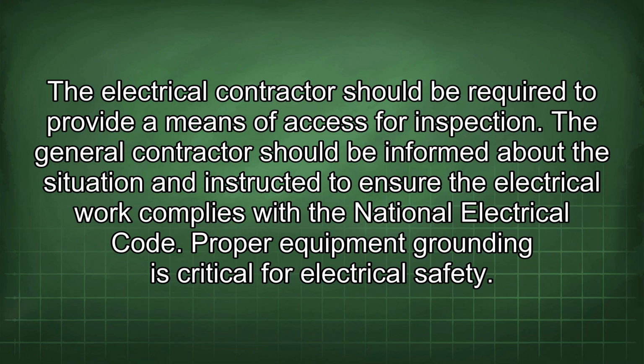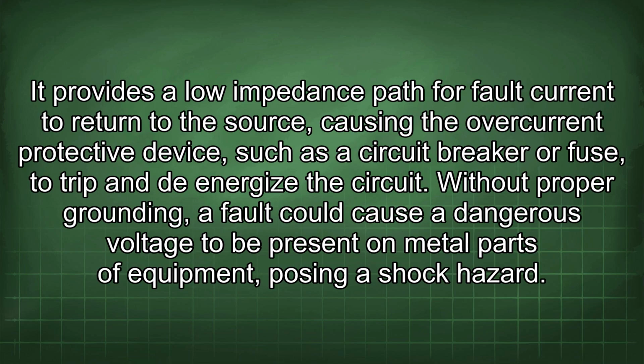The general contractor should be informed about the situation and instructed to ensure the electrical work complies with the National Electrical Code. Proper equipment grounding is critical for electrical safety. It provides a low-impedance path for fault current to return to the source, causing the overcurrent protective device, such as a circuit breaker or fuse, to trip and de-energize the circuit.